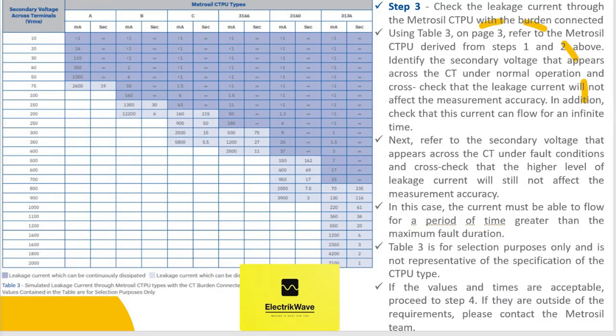As per Step 3, check the leakage current through the Metrosil CTPU with the burden connected. Using Table 3, refer to the Metrosil CTPU derived from Steps 1 and 2 above. Identify the secondary voltage that appears across the CT under normal operation and cross-check that the leakage current will not affect the measurement accuracy. In addition, check that this current can flow for an infinite time.